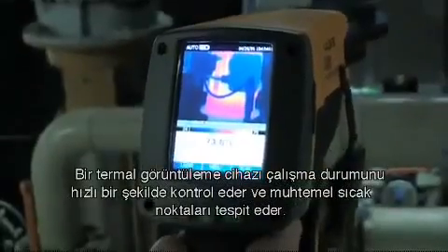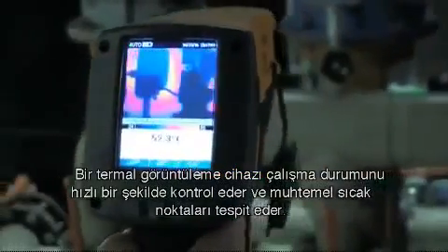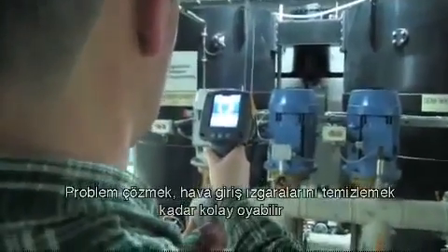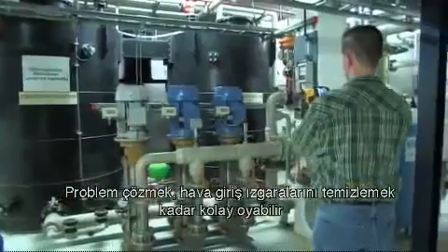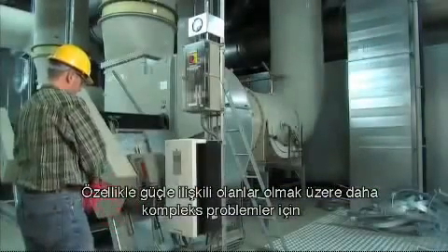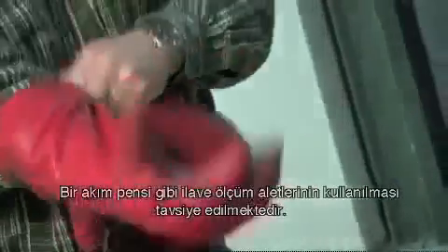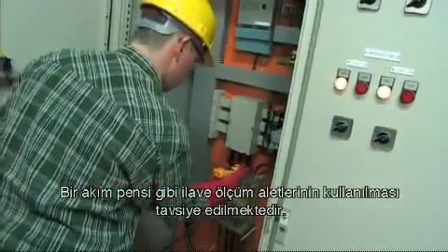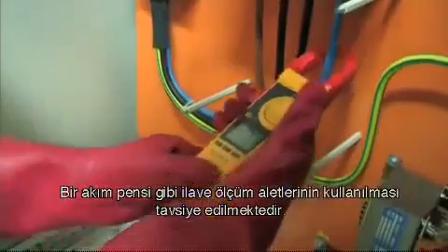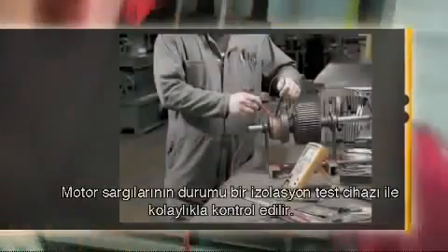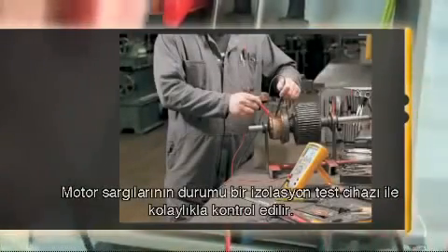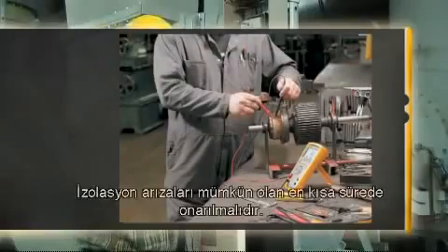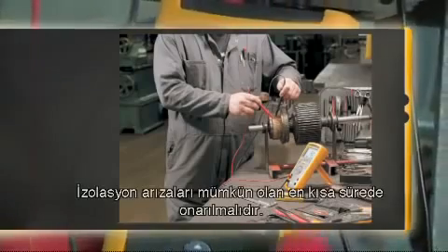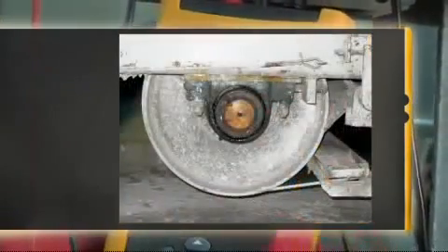A thermal imager quickly checks the operating condition and finds possible hotspots. Problem solving may be as easy as cleaning the air intake grills. For more complex problems, especially those related to the power, it's advisable to use additional measurement tools like a current clamp. The condition of the motor windings is easily checked with an insulation tester. Insulation failures should be repaired as soon as possible.